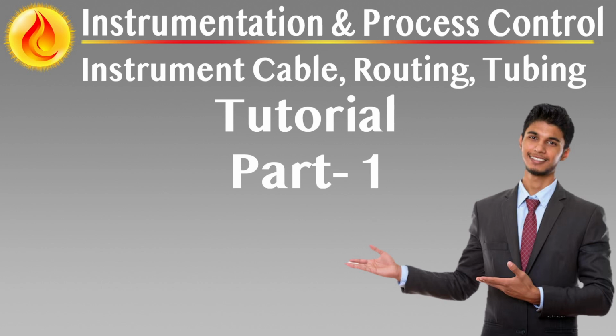Cables for such devices often must avoid intermediate terminations like junction boxes or MDFs. A continuous run from transmitter to receiver is recommended to preserve signal quality and reduce insertion loss. Manufacturer guidelines must always be followed regarding cable type, length restrictions, grounding, shielding, and installation routing.